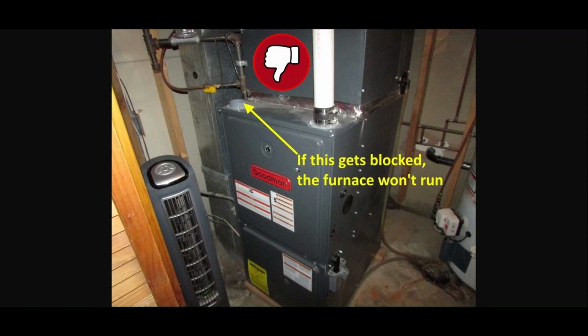So this is not something you're going to notice right away. Down the road, you're going to get a no heat issue. Someone's going to come and say you got a bad heat exchanger. If there's a lot of dust and debris in the air in whatever room this is in, and keep in mind this is suction, so it's going to suck it in. It's going to bring it into the burner and then kind of snowball effect and wreck your heat exchanger. So it's not always possible to two pipe furnaces, but I always try and do it, or we always try and do it at Central Heating, just to make sure down the road there's not an issue.